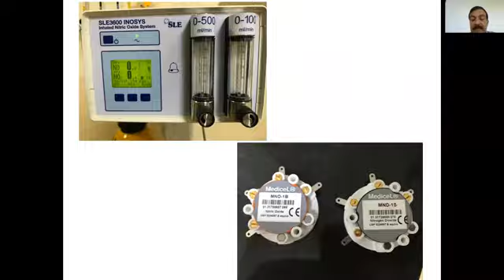And once it is done, then we use another second canister to calibrate the nitrogen dioxide, up to the maximum 5 parts per million. And this calibration has to be done every 28 days throughout the year. And this is usually done by our service biomedical engineer.